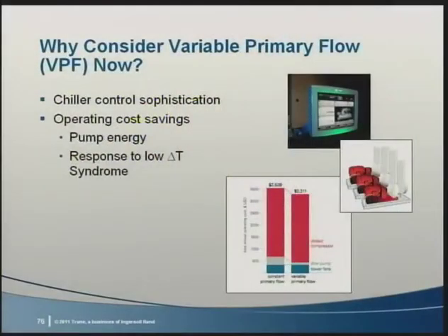If people haven't used systems that allow variable chiller evaporator flow rates in the past, why are they being considered today? Now, first and foremost, in the past, manufacturers told you to maintain constant flow through the chiller's evaporator. Today, sophisticated feed-forward control allows the chiller to react quickly to changing conditions. Therefore, some new chiller controls accommodate varying evaporator water flow rates.